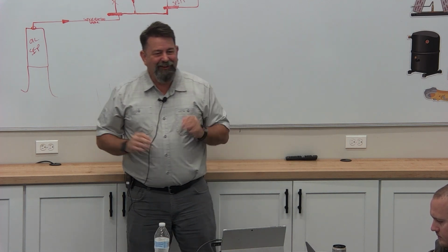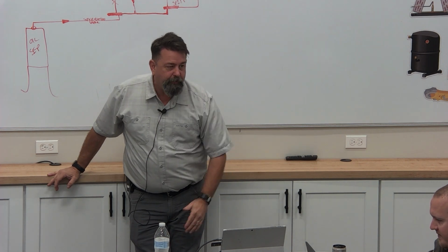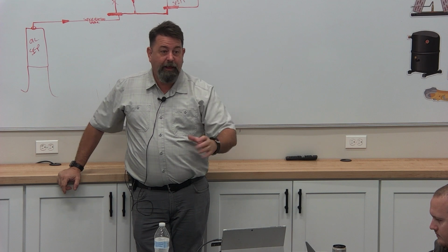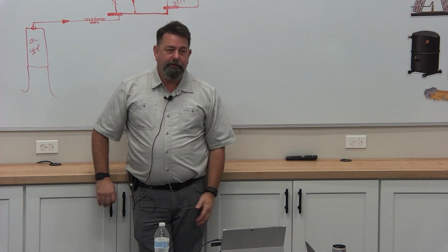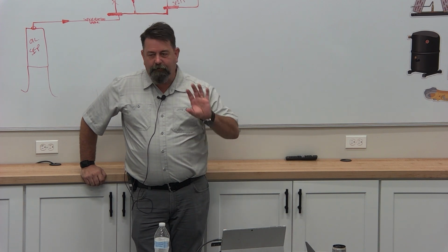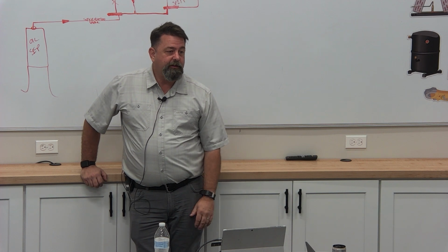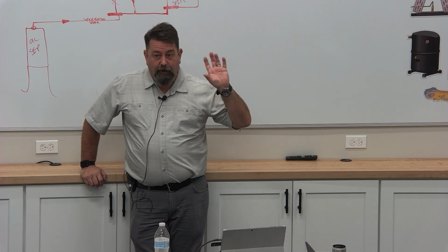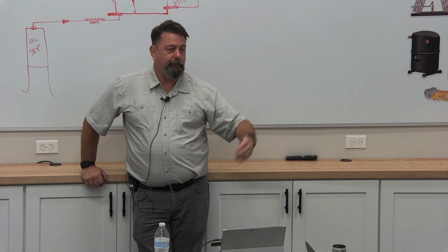A huge problem similar to that in Dixie. Why? Because it's a different shelf than they designed for this airflow. That means my wall is not at design. Can it work? Yeah, it can work, right? If we get everything just right. And in that case, I may have to put product in that case. If I'm using an unauthorized shelving system, I'm almost for sure going to have to put some product in that case.